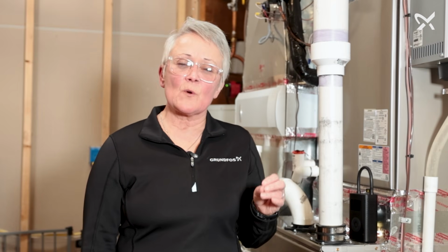When making the connection for your stainless connectors, you want to make sure that you're using a thread sealant that's approved for PVC threads. Teflon tape is great, but be sure that you don't overwrap it. We need to be able to feel those threads through the Teflon tape to ensure that we're getting a nice tight connection at the fitting. If you're using a flex connector that has an O-ring seal, you don't need a thread sealant. The O-ring will be sufficient. And if you're using a paste, don't use a hard setting thread sealant because it could potentially create a leak path.